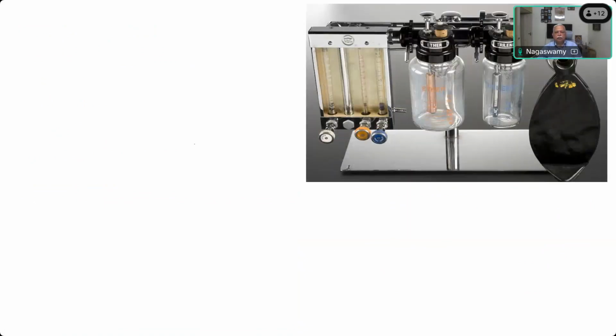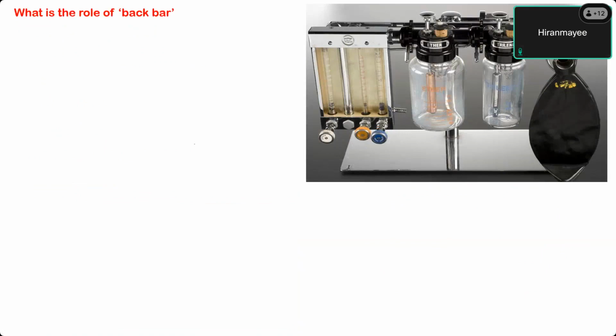This is a very old type of anesthesia machine, which many of you would not have seen. So what is the role of the back bar in these machines? It is to hold the flow meter and the vaporizer, sir. So it is all fixed on the back bar only. The flow meter assembly, the two vaporizers, ether and trilene, all these things. This is what I told you. This is called the trilene lock.